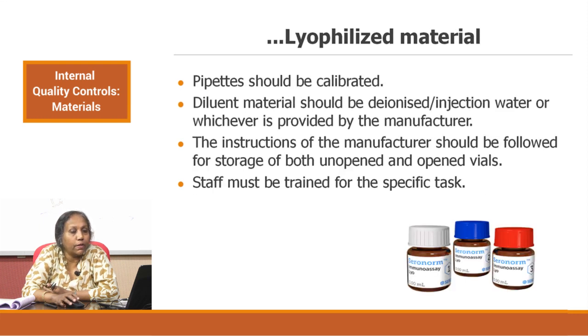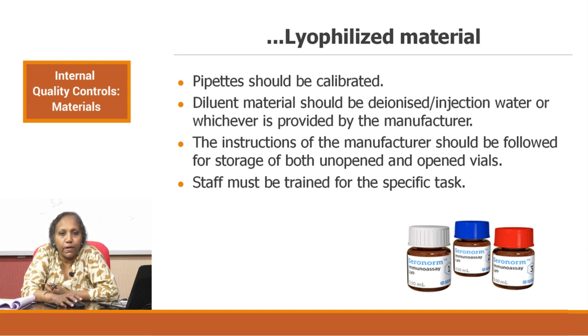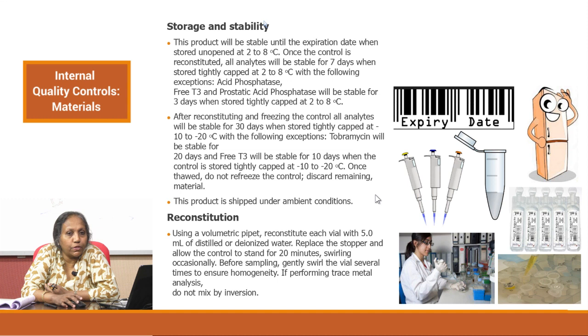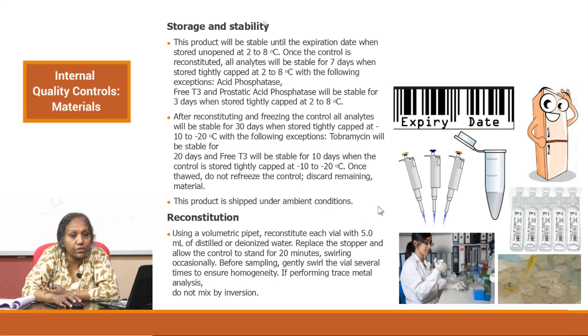Other things to keep in mind: the pipette should be calibrated, diluent material should be deionized water or injection water or whichever is provided by the manufacturer. Instructions of the manufacturer should be followed for storage for both unopened and open vials. Understand how to store it before opening and after opening, what the stability is, and the staff must be trained for the specific task. Read the insert very carefully, especially with regard to storage and reconstitution instructions.